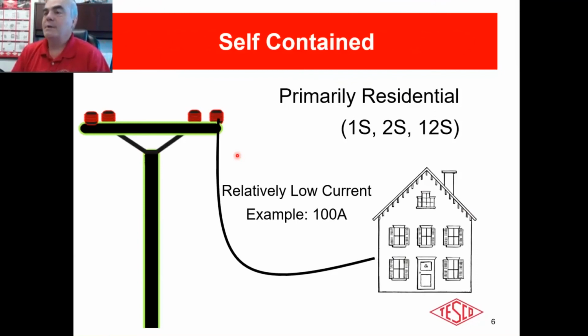All right, self-contained. Primarily, this is our residential, 1S, 2S, 12S. Relatively low current. So for example, this house right now is drawing 100 amps. That's actually quite a bit. Most of our homes, we're typically pulling a couple of amps, 10 amps, 20 amps, 30 amps. You plug in your electric car, you might be pulling 48 amps. So actually 100 amps means you've got all the ACs going, you're pulling a pretty good load. Most of our meters are 200 amps or class 200. The meter is right in line. If you remove the meter, you're basically disconnecting the power, unless you put in some jumpers.